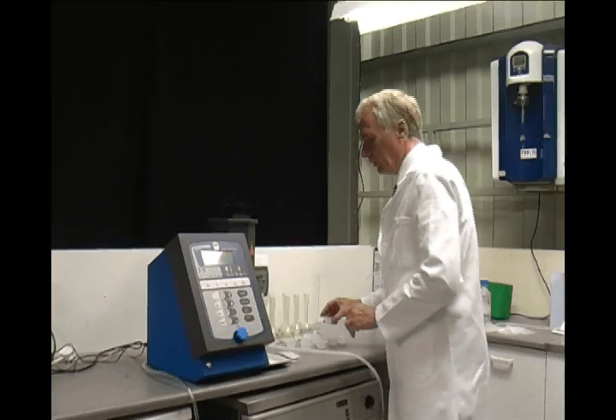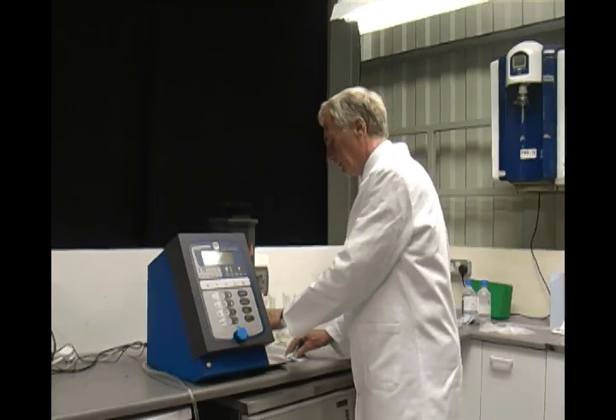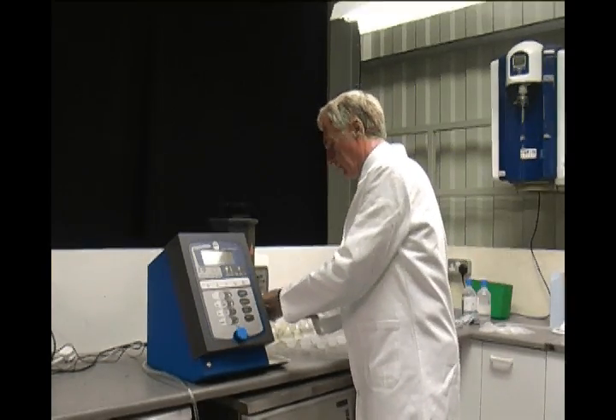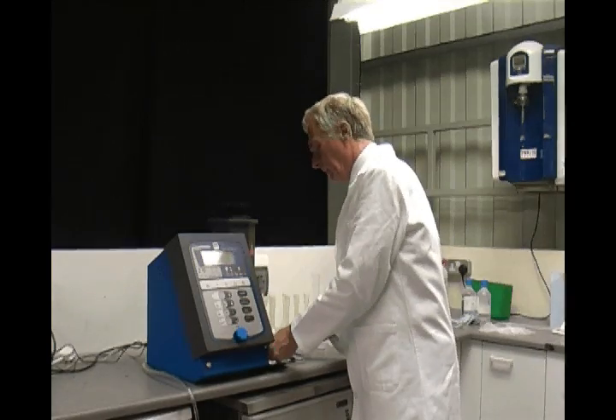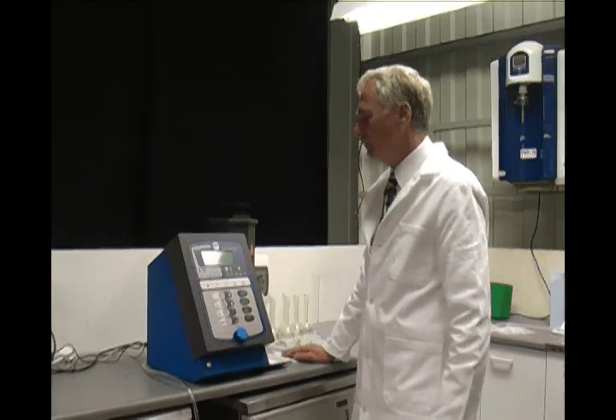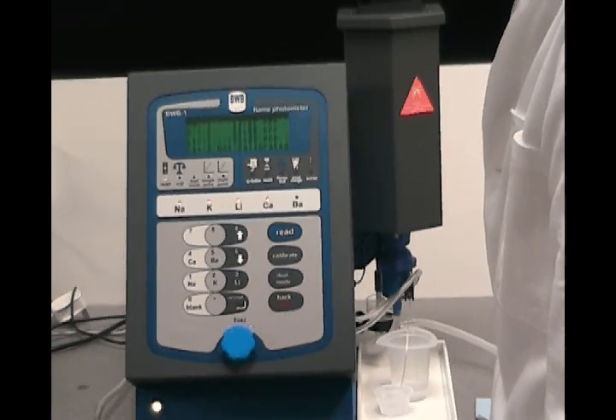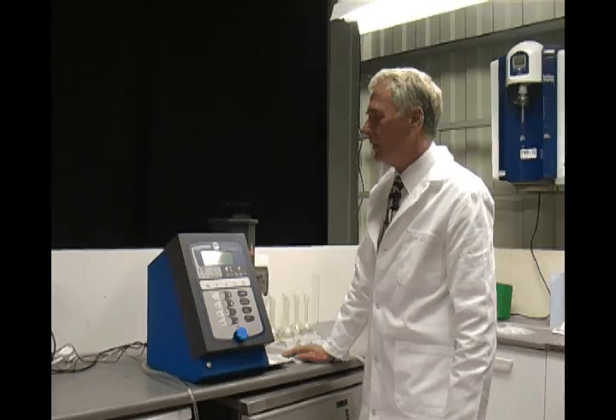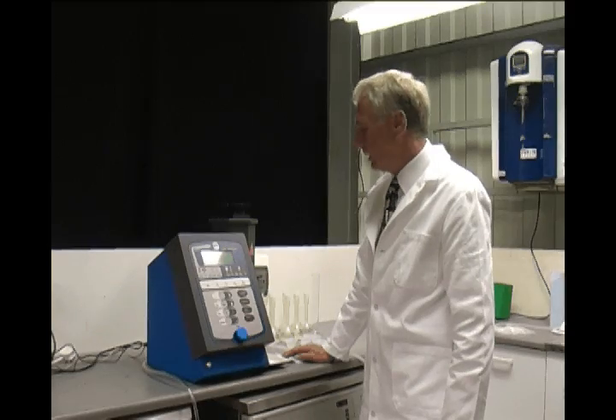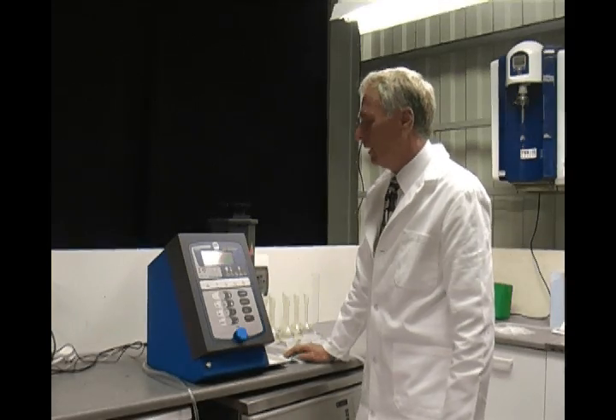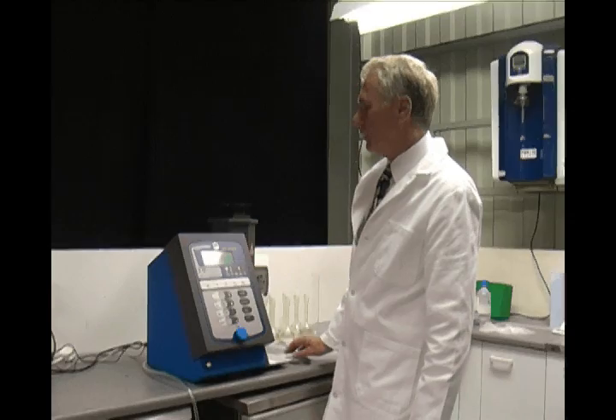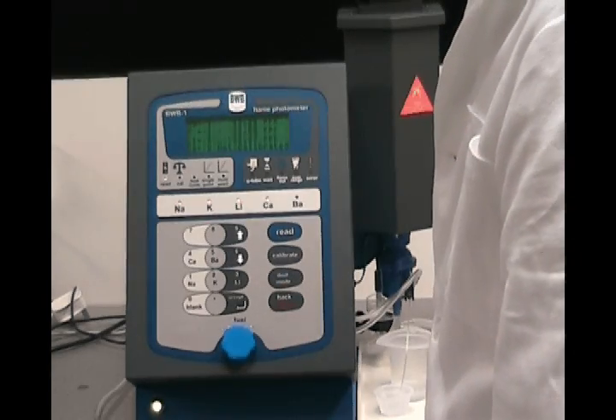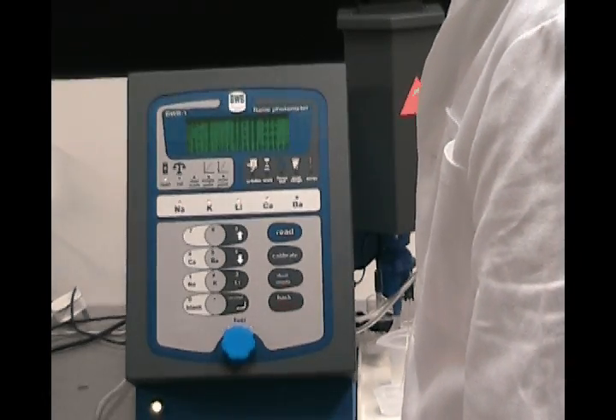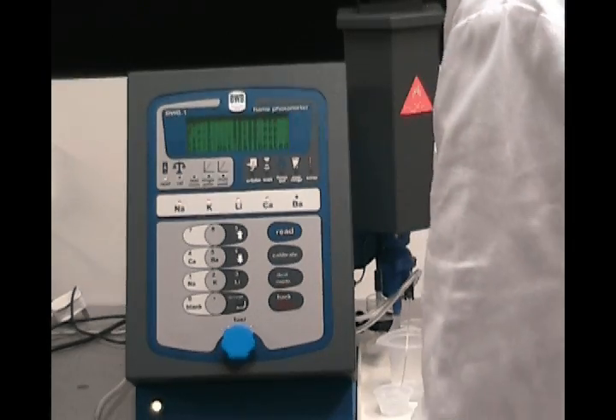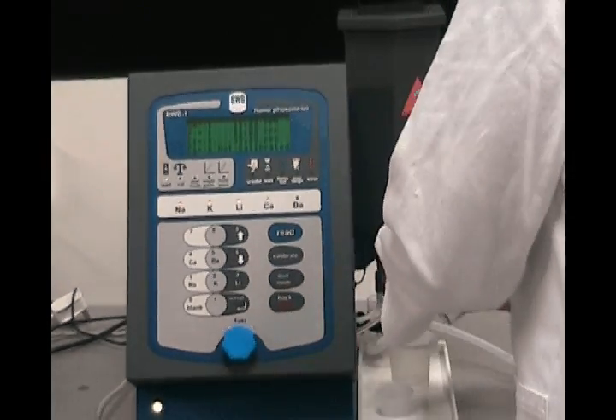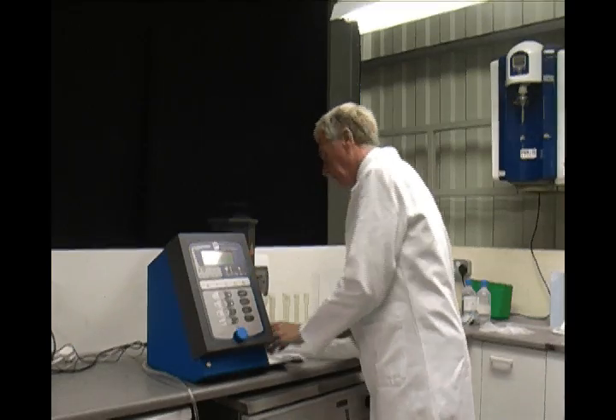Lastly, to another sample that was prepared earlier. This once again is a mixture of sodium, potassium and lithium. This should be 10 ppm sodium, 20 ppm potassium and 30 ppm lithium. We've now reached a stable reading, which is telling us 12.20 on sodium, 21.12 on potassium and 33.91 on lithium. Back into the DI.